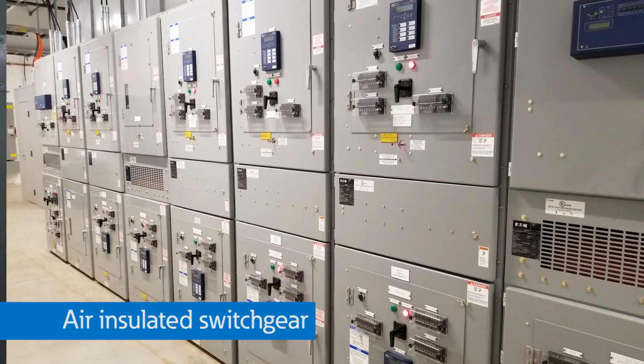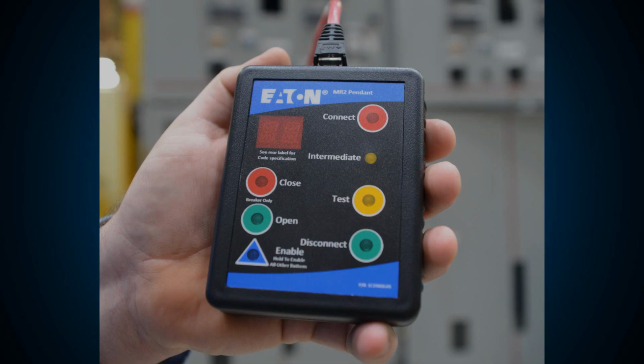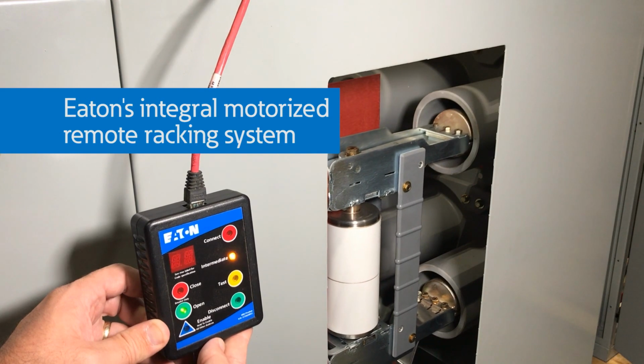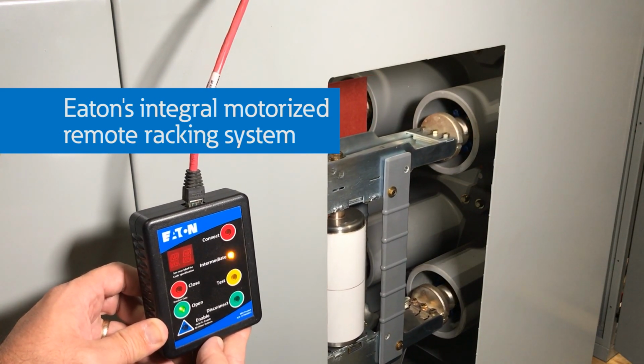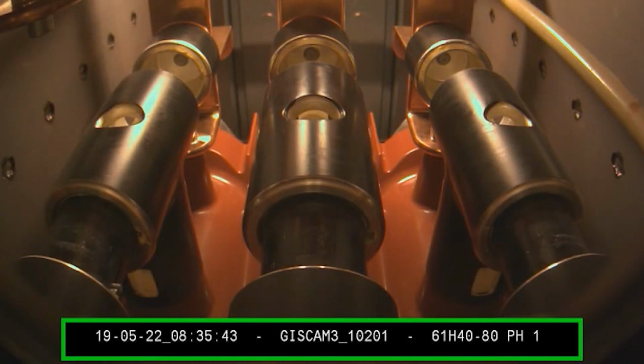the 3-position switch. In air-insulated switchgear with withdrawable circuit breakers, such as IEEE rated metal-clad switchgear, after a circuit breaker is opened, an operator may move the breaker to any of the disconnected, test, or connected positions. These operations can be performed either manually or remotely using a system such as Eaton's integral motorized remote racking system. In a similar manner, in gas-insulated switchgear, the operator can move the 3-position disconnector switch to the closed, open, or ground positions either manually or electrically.